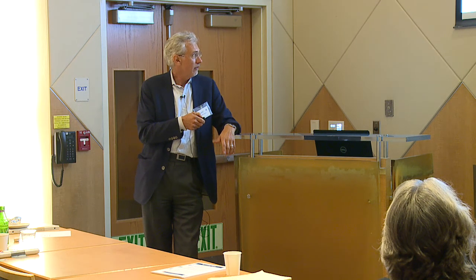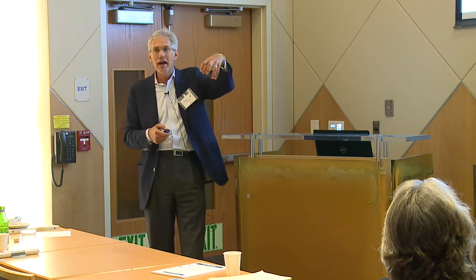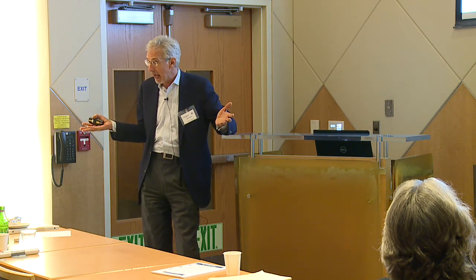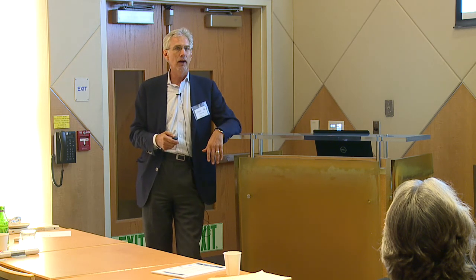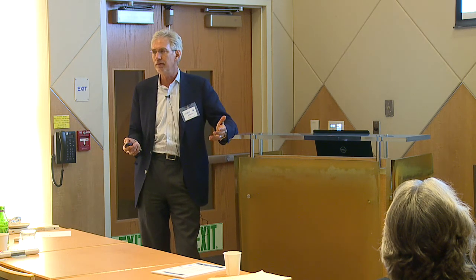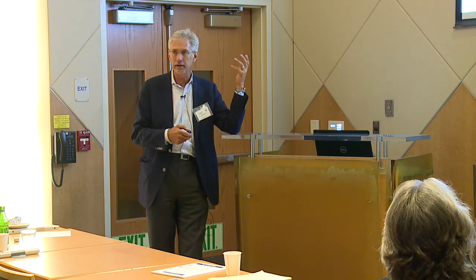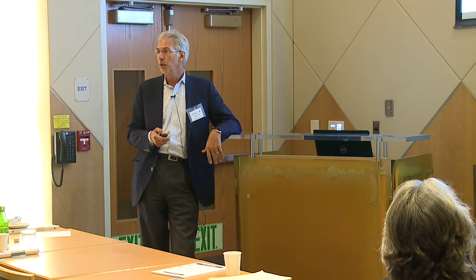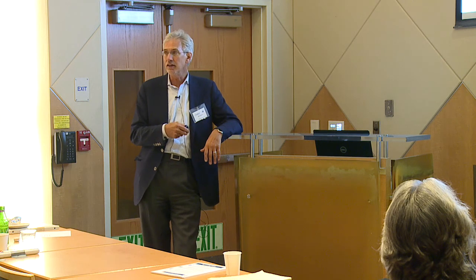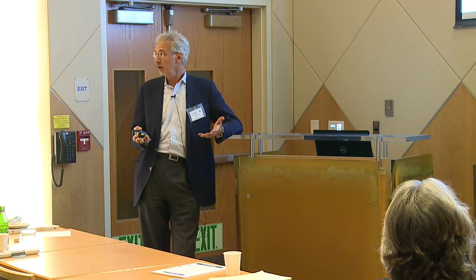This engine right here, it's not to scale, but this has got 18 cylinders. It's about 1 megawatt per engine. They burn gas. These are originally adapted from marine diesel. Well, now they fast start. You can start them up in 5 minutes. They have good part load efficiency. They burn gas, so they're clean. They have catalytic reduction controls on the back end. And you're seeing these put in for balancing the wind and solar. And in some cases, you're seeing them put in to replace other baseload capacity, like a retired coal plant.